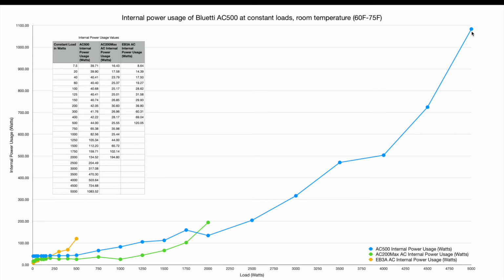Go back to the well pump example. You've got a 2,500 watt or 1,500 watt well pump, but it only runs for 2 minutes. The fans don't even turn on because it doesn't get hot enough inside. This is worst case scenario, where that 5,000 watt load is running the entire time, from when the battery starts until it gets to 0. I'm really pushing this thing hard to see how much cooling I can get out of it. So these internal power usage numbers are worst case scenario, which is why they're so high here, but this is still pretty impressive.